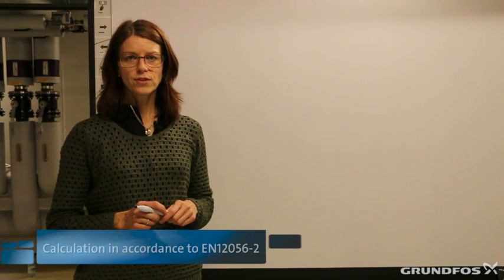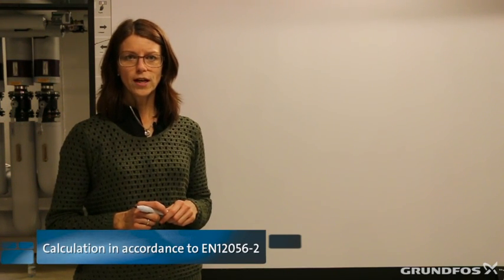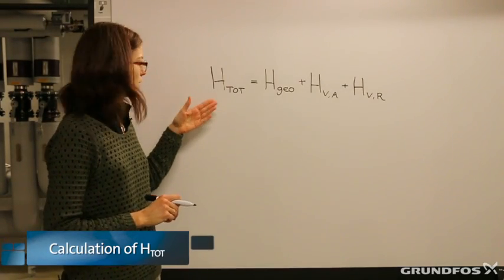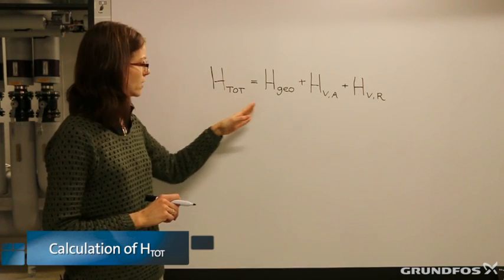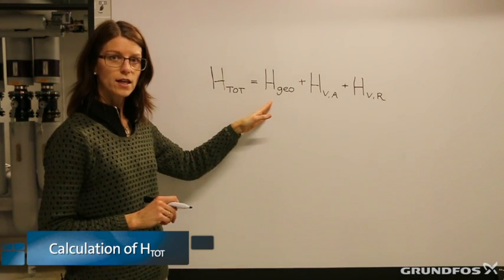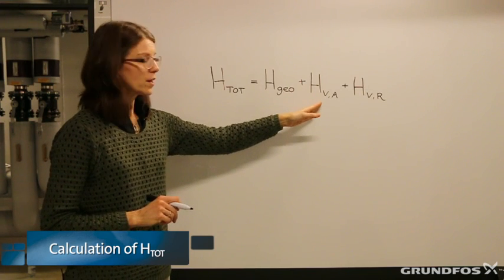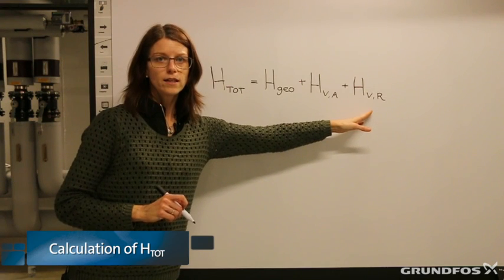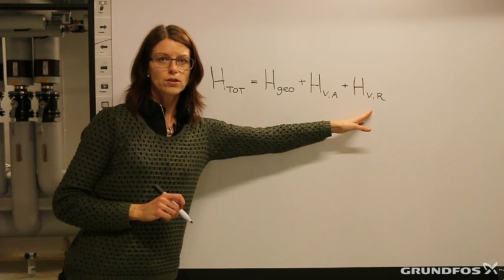I would like to show you how to calculate the required head in a wastewater system in a commercial building. In the EN standard 12056-2, we will find the formula to be used for that. The formula shows that the total head is the sum of the geodetic height in the system, the friction loss in the valves and fittings, and the linear friction loss in the pipes.